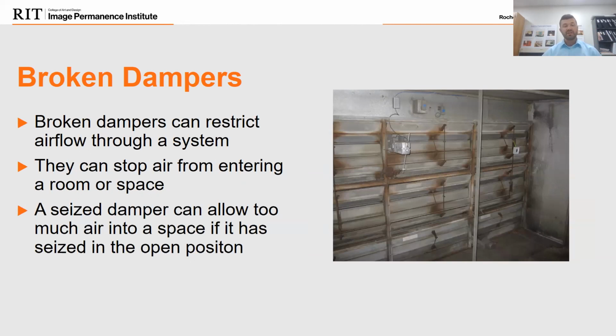And we'll work with an institute that says, hey, it's stuffy, there's poor air movement, I have a microclimate. And many times it turns out that the fire dampers have failed, or even the outside air dampers have closed and have rusted shut and they're just not opening. So broken dampers can be a major fault and a major cause for either poor airflow or lack of outside air, things like that.